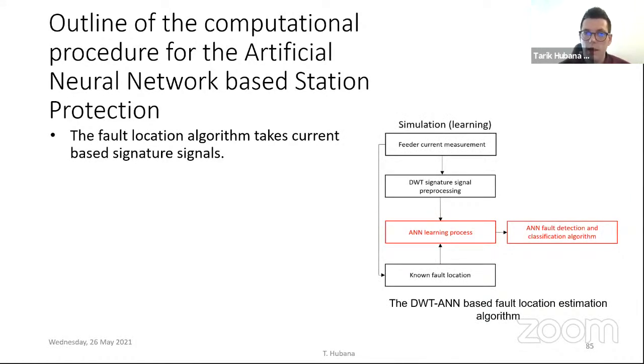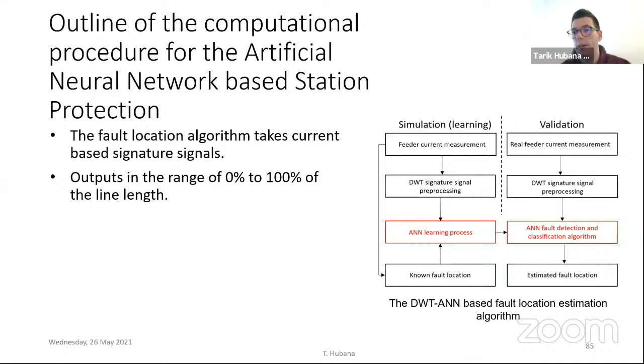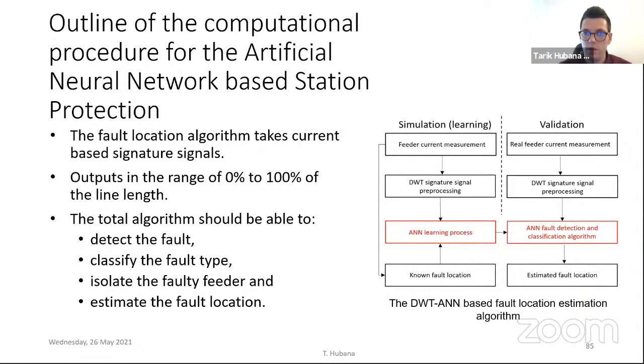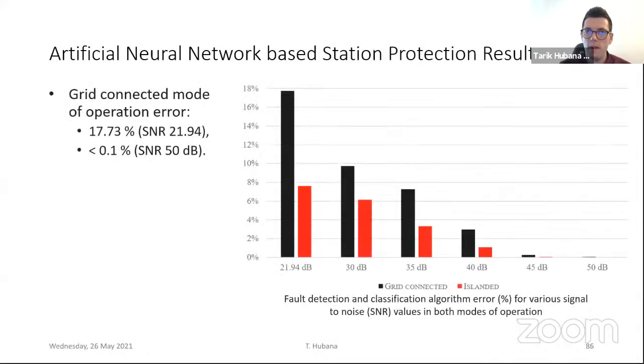Another functionality that was added was the fault location algorithm, because it is extremely important in the distribution system operator regular work to know the exact fault location in order to quickly repair the fault and continue with the supply. This algorithm actually used current measurements, again pre-processed with the DWT signal pre-processing, and now having a different output, since this wasn't a classification problem for the neural networks, and the outputs were in range from 0 to 100% of the line length, where the percentage indicated at which place the fault occurred. So after implementing all of these functionalities, this algorithm should be able to detect the fault, classify the fault type, isolate the faulty feeder, and estimate the fault location. And let's see the results.